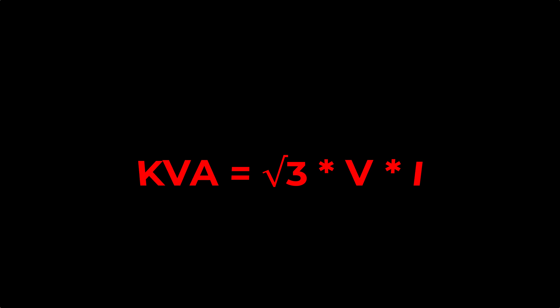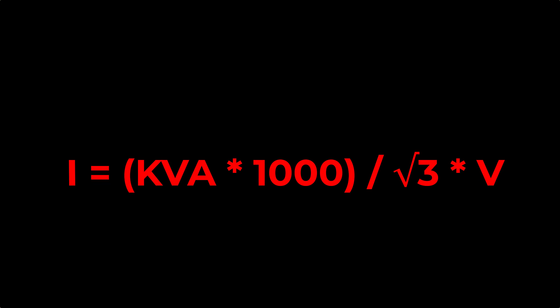First of all, you need to know the KVA formula. The KVA formula is: KVA = √3 × V × I. Rearranging to solve for current, the formula becomes: I = (KVA × 1000) / (√3 × V).